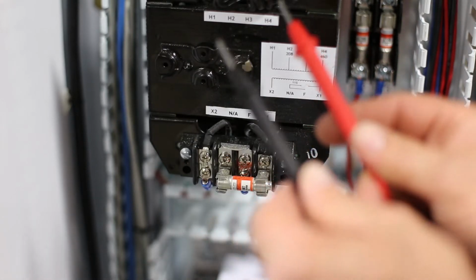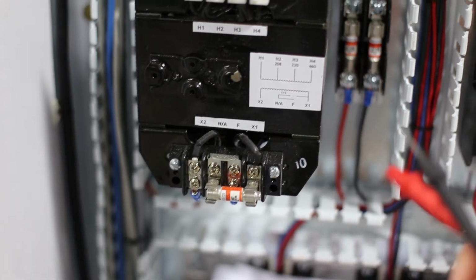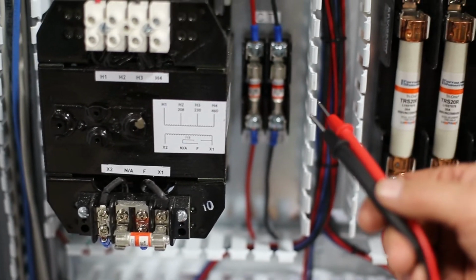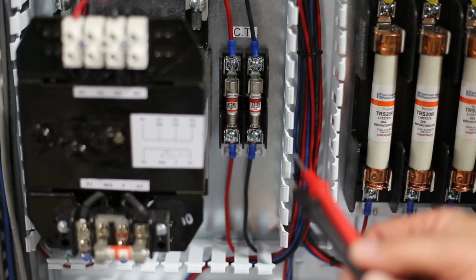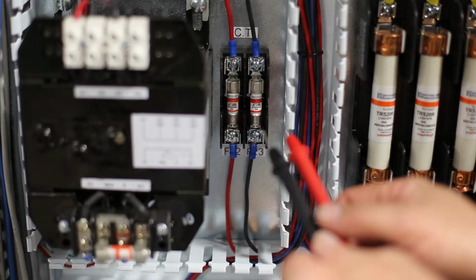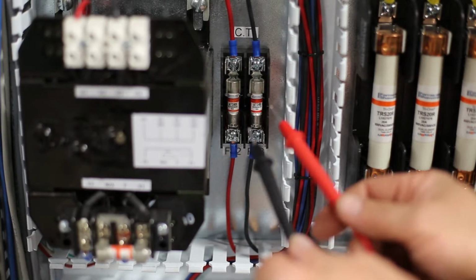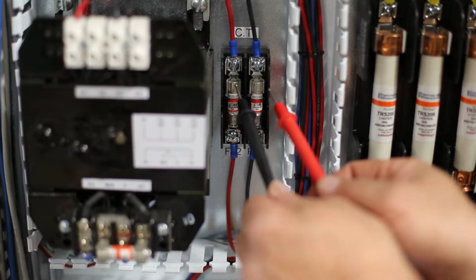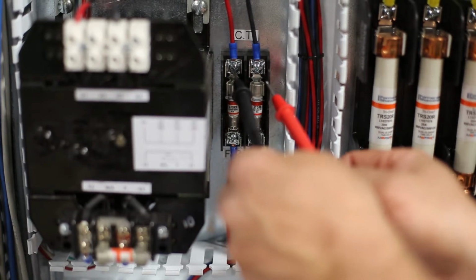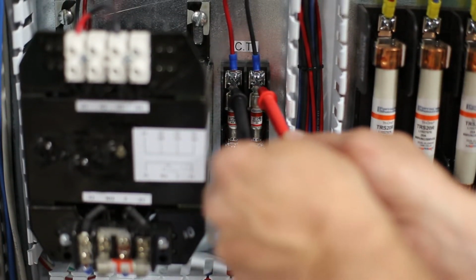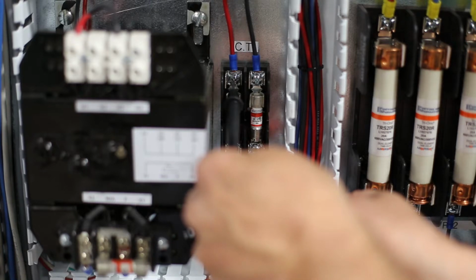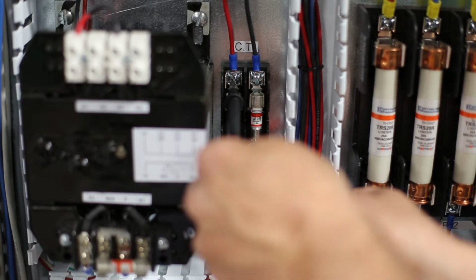Now, if we do not have power to the primary side, we have to look for our primary fuses. Generally, we have 2 fuses for single phase. So what you'd want to do over here is check from the top of the first fuse on both of them, between leg 1 and 2. You should have, in this case, 240 volts. Then drop down to the bottom of the second one, and from the top of the first one to the bottom of the second one, you should still have 240 volts.